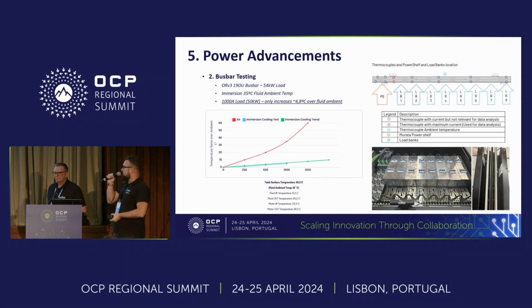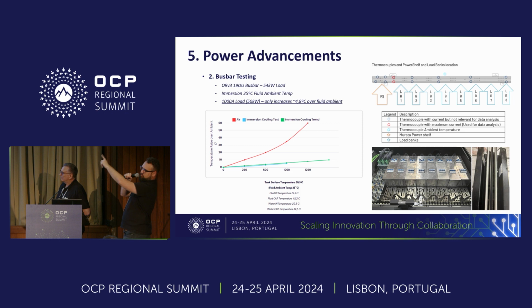The testing setup shown here, down at the right, is the testing pod. There's the power shelf Kevin was discussing at the left, and the dummy loads at the right generating the proper load to consume 54 kilowatts. Of course, we didn't do this with real servers because it's very expensive if something goes wrong. So on the busbar up there, we put thermocouples to read the temperatures in different parts of the busbar and understand what was going to happen.